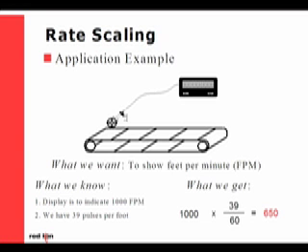Our example means to display feet per minute of a process. Our fastest rated speed is 1000 feet per minute, and 39 pulses per foot are given off from our sensor. Our rate input then becomes 1000 times 39 over 60, or 650. We would then enter in the programming 1000 for a display, and 650 for an input.